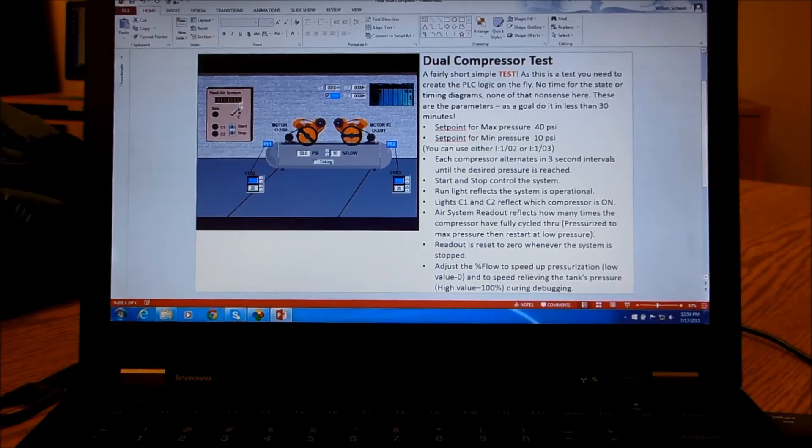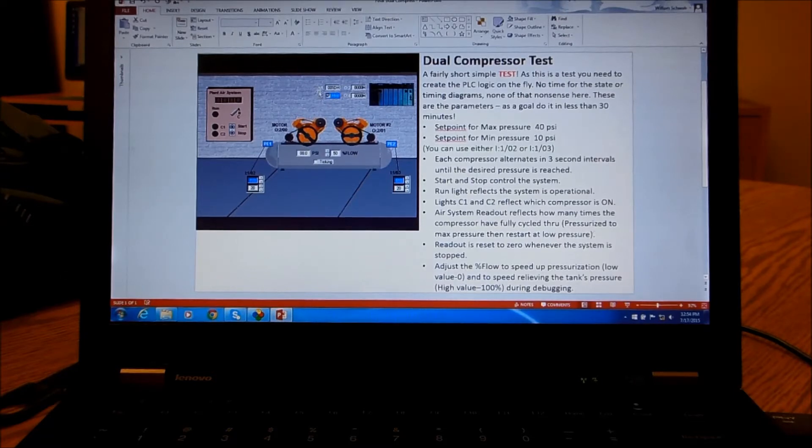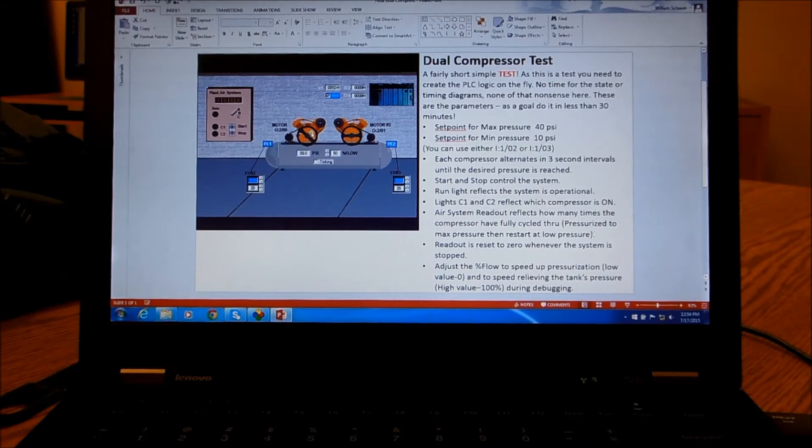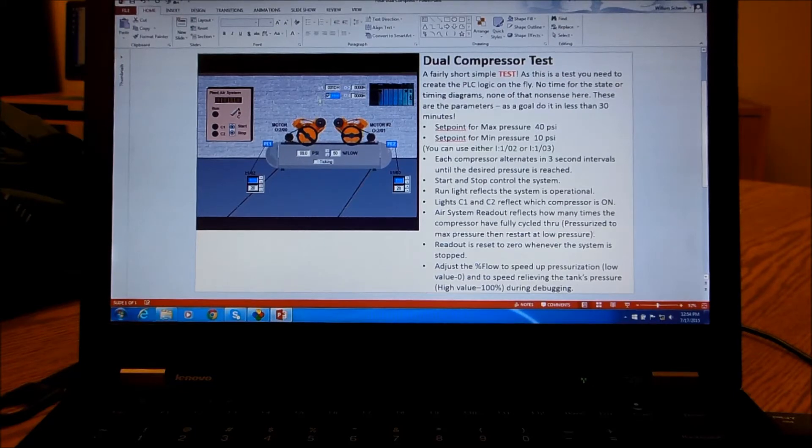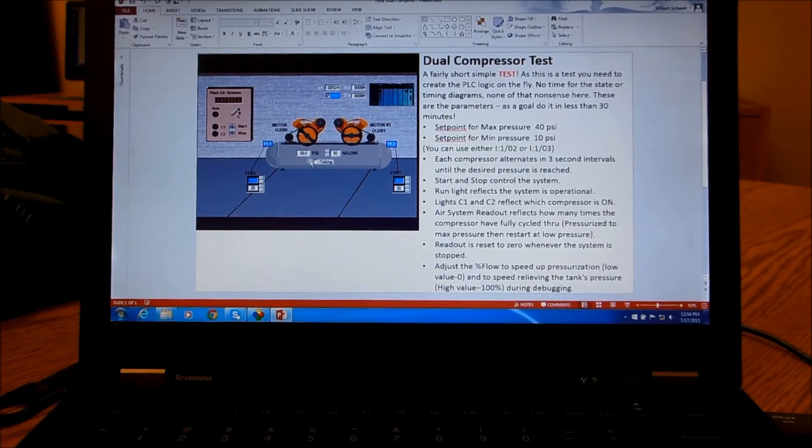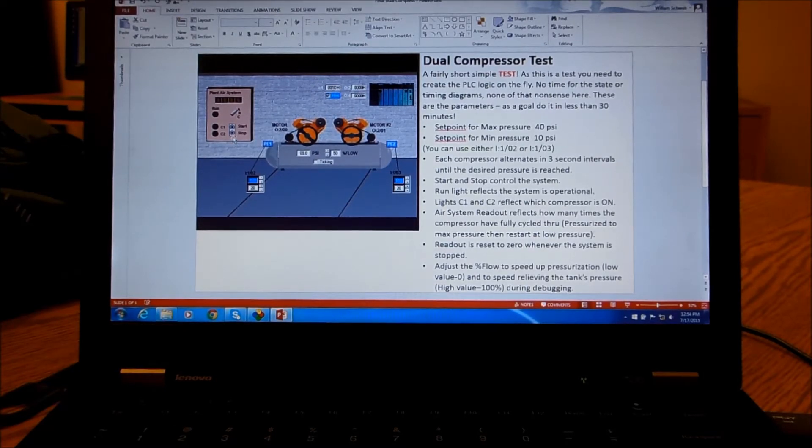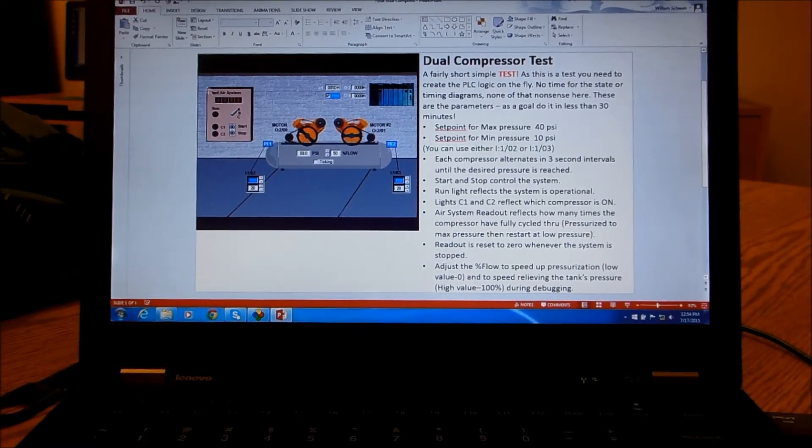The only last thing for this demonstration: when the compressors cycle they go fully up to pressure and then all the way down when it drains. Then when it turns back on, every time it goes through one full cycle it counts. So it counts when it first goes up and then goes down, and it counts to two the second time it starts and completes the cycle. Our stop button stops the process and also resets our counter to zero.